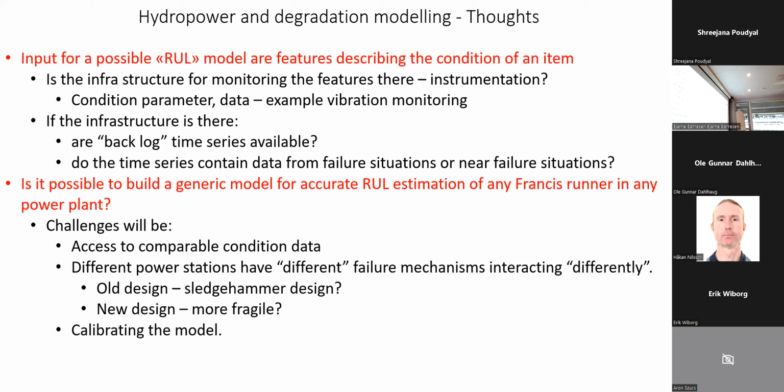And I won't go into details with this Lima incident, but we could see a significant difference in the thickness of the blades between the one that cracked and the one they used to replace it. Significant. And the old stuff is often sledgehammer stuff. The turbine wheel had been sitting since, I think, 73, was replaced in 2006 or so. And then after eight hours, it went wrong.